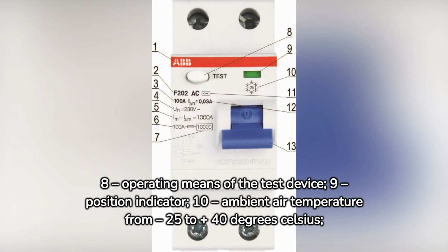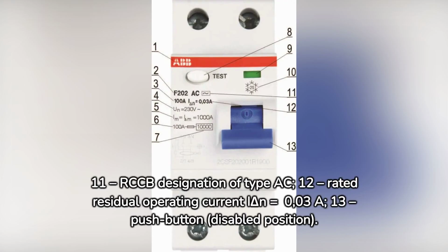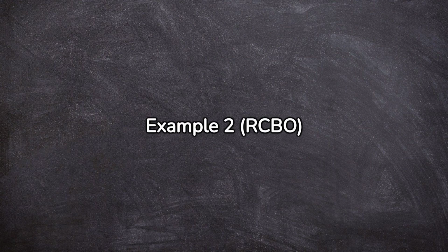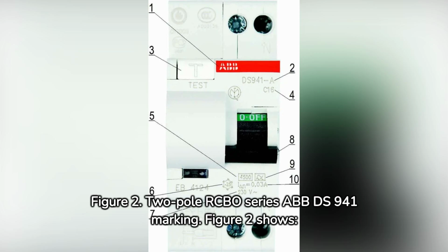8. Operating means of the test device. 9. Position indicator. 10. Ambient air temperature from -25 to +40 degrees Celsius. 11. RCCB designation of type AC. 12. Rated residual operating current IΔn equals 0.03. 13. Push button, disabled position. Example 2, RCBO. Figure 2.